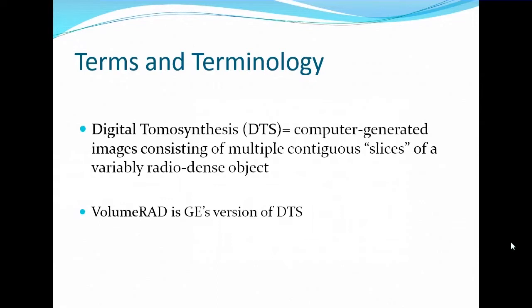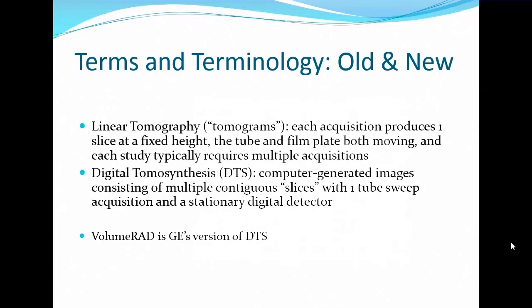It's always best to start with terminology so we're all on the same page. Digital tomosynthesis, or DTS, is a modality consisting of computer-generated images of multiple contiguous slices of variably radio-dense objects like the human body. VolumeRAD is GE's version of it. The old-school linear tomography involved multiple acquisitions with a tube and plate moving in opposite directions, whereas the digital version generates multiple slices with one tube-sweep acquisition and a stationary digital detector.